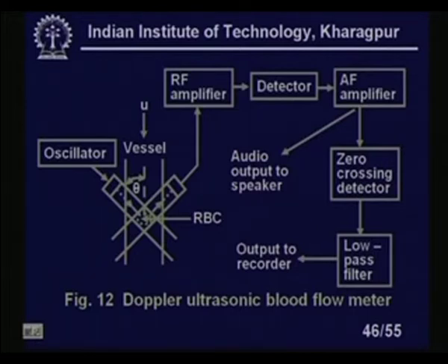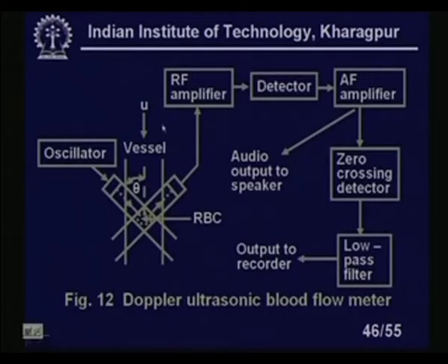Okay. There are two types of frequency; we will get zero crossing detectors. We have low pass filters and output detectors, because the added frequency will be deleted, and the difference of frequencies, which is very small, will be passed. All other frequencies will be stopped. So, this is actually the entire scheme of our ultrasonic flow meters for measurement of blood flow using the Doppler shift method, right.